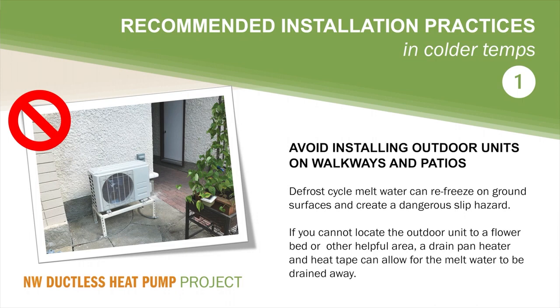And you will likely need to apply thermostatically controlled heat tape to this drain pipe to allow the meltwater to be drained freely away. While an icy, frozen patio or sidewalk may not impact system energy savings or heating performance, it does make customers unhappy with their heat pump system. And unhappy homeowners are likely to tell their friends and family all about it. This is bad for homeowner electric savings in the end, and bad for heat pump business too. So be careful when locating your outdoor units.